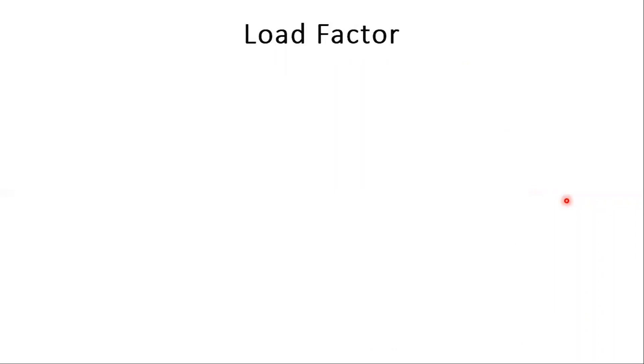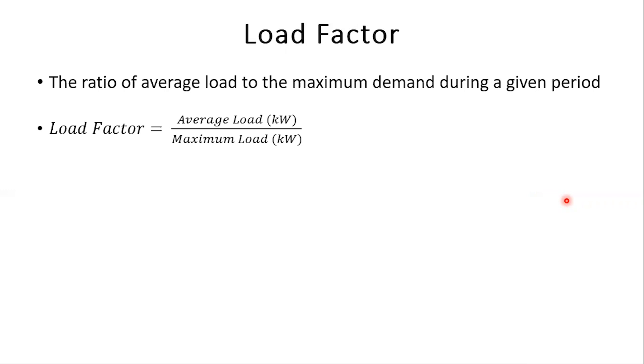Moving on to the theory, we'll first look at the load factor, which is defined as the ratio of average load to the maximum demand during a given period. Mathematically, load factor equals average load divided by maximum load. By multiplying both the numerator and the denominator by the time duration, we can arrive at the expression shown here.